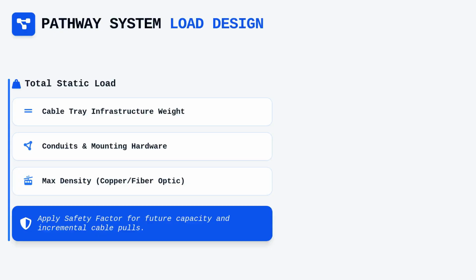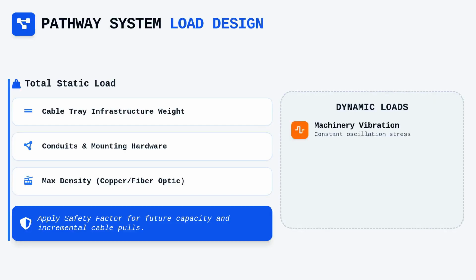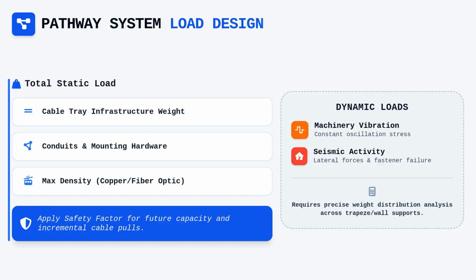We must apply a factor of safety to these static loads, accounting for potential future cable pulls that could incrementally increase the load on the supports. Dynamic loads must also be considered, particularly in environments where machinery causes vibration or where seismic activity is a credible risk factor. A tray system that is secure under static conditions may fail if the fasteners are not rated to handle the lateral forces exerted during a seismic event. Calculating these forces requires a precise understanding of the weight distribution across the span of the trapeze or wall-mounted support.